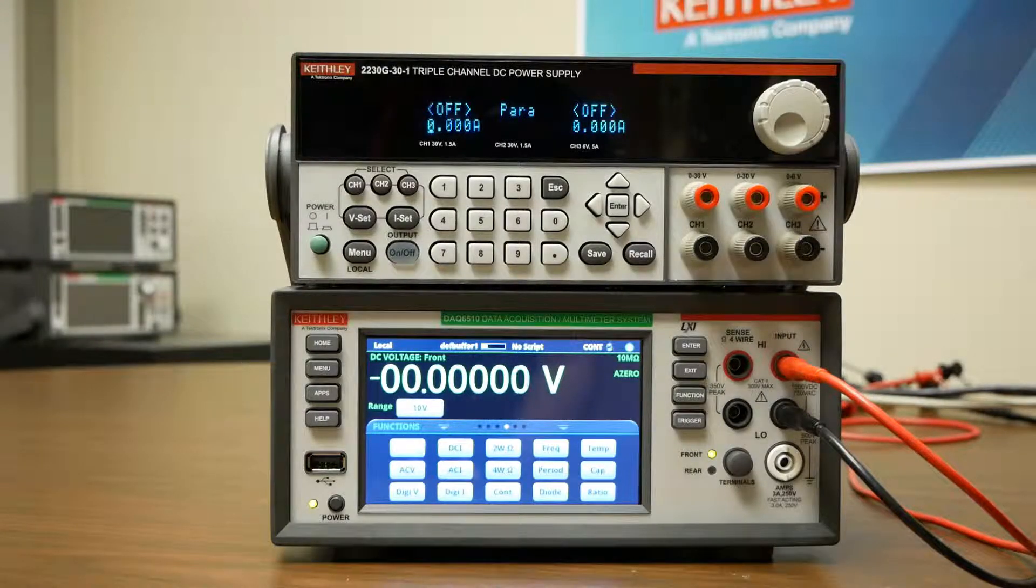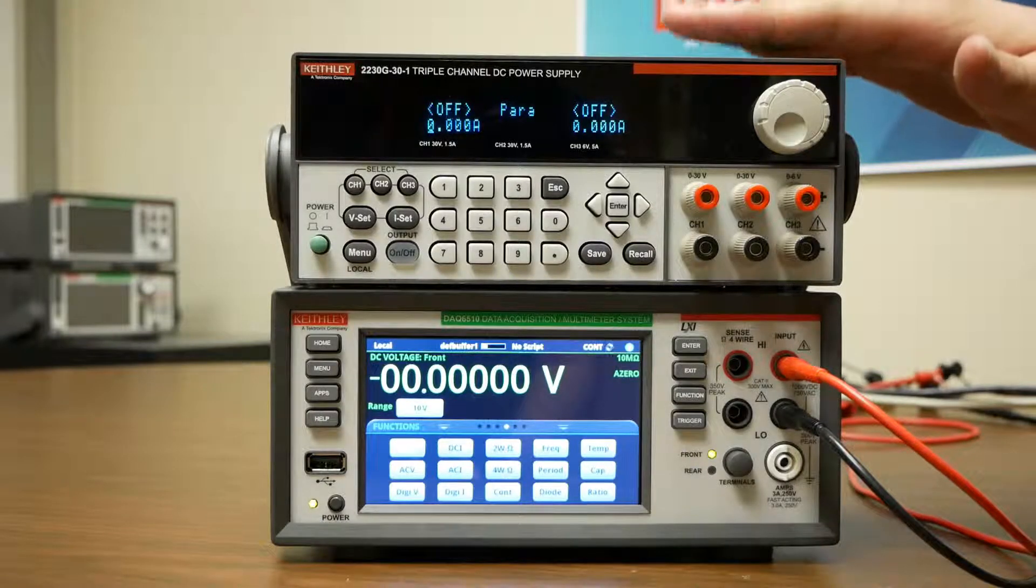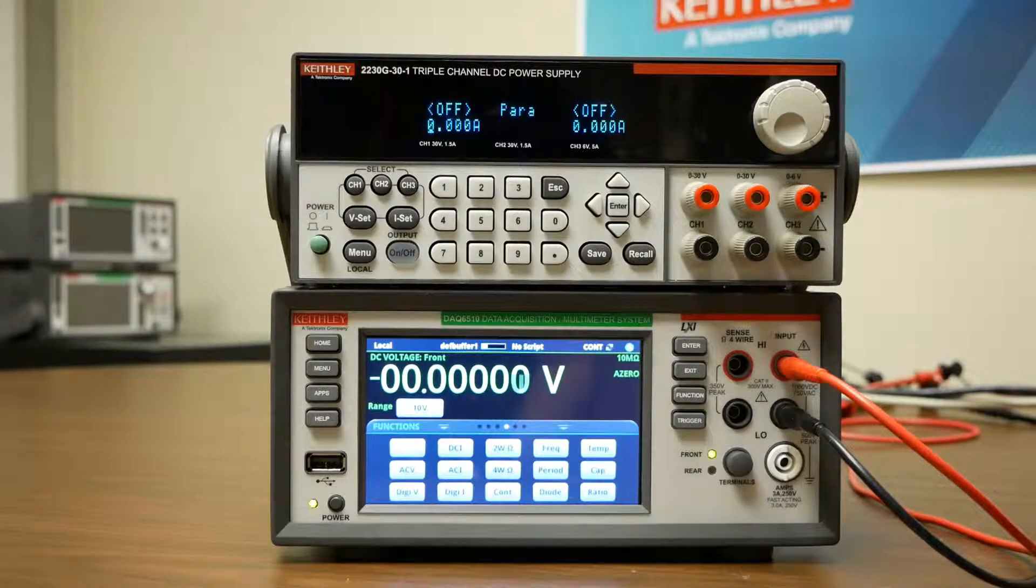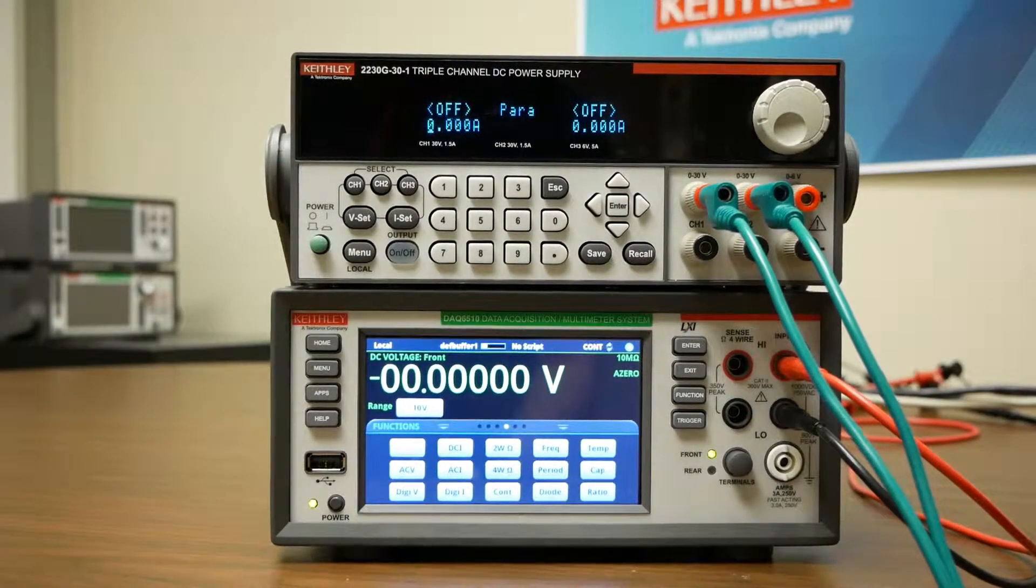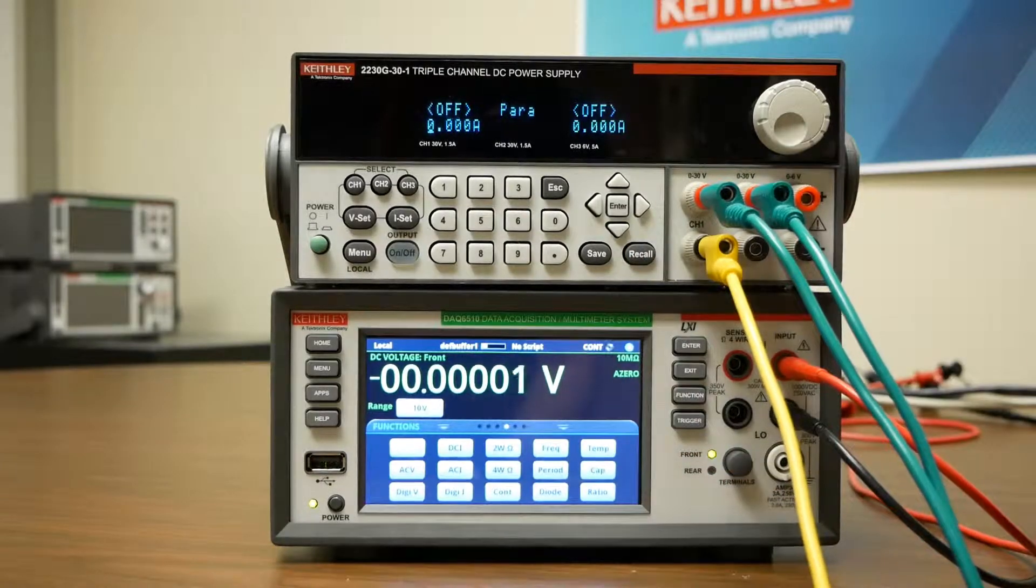Now we're going to make our front panel connections and we're going to configure our parallel test settings. First we'll connect our channel 1 and channel 2 high and our channel 1 and channel 2 low.